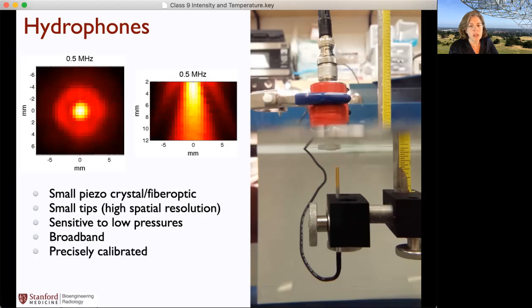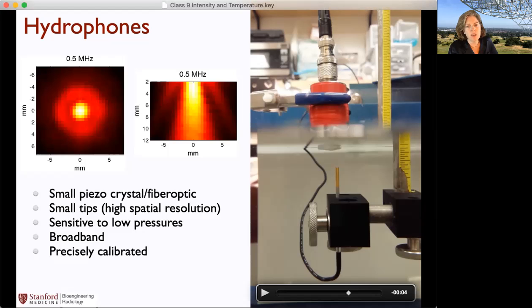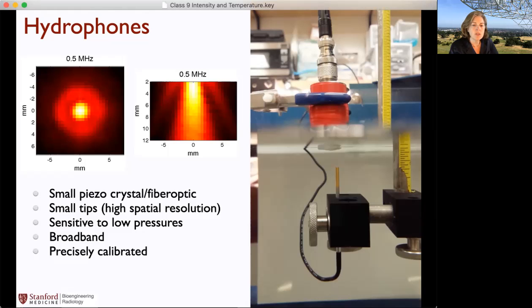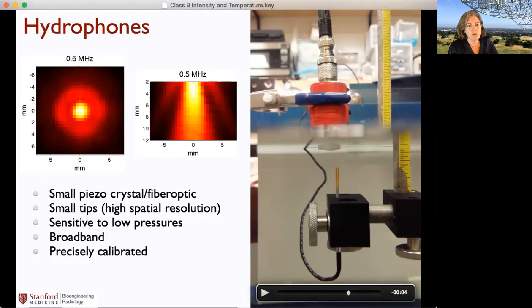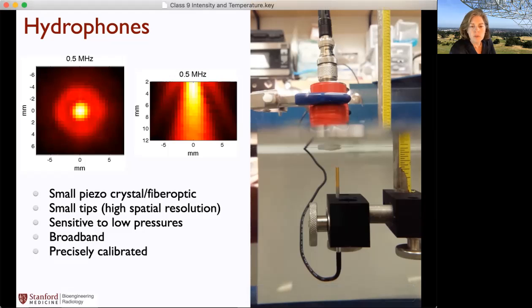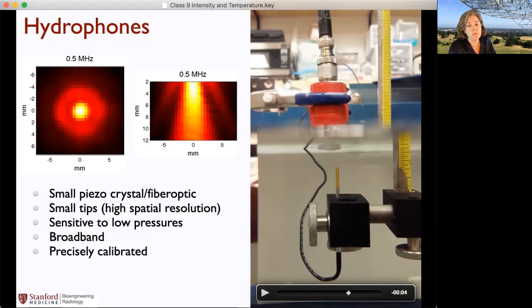They're typically very broadband, and oftentimes you send out a short pulse. If you were to send out a continuous wave, that would potentially be more damaging to the hydrophone. So oftentimes very, very short waves. And they're also very precisely calibrated. Every time we have new transducers, we have a fiber optic hydrophone, and every time we purchase more, they have to recalibrate the whole system, because we really want to make sure we get very good measurements, so they're calibrated very precisely.